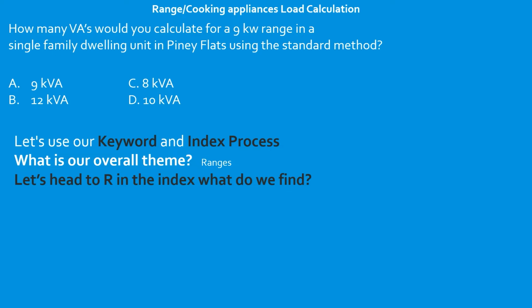And there's a couple different things listed here. Let's go ahead and look at them. It says Article 220.55, and then it says Table 220.55. They're matching, so we can keep a piece of paper in the back of the index just in case we need to get back there. But there's no conflicting code articles, so we're probably in the right section. So let's go ahead and head over to Article 220.55. Take a minute, pause the video if you need to, and we'll catch up when we get there.